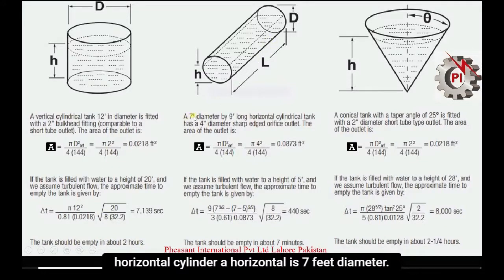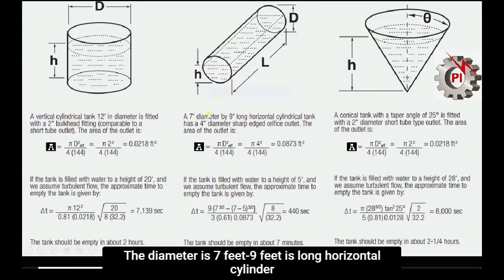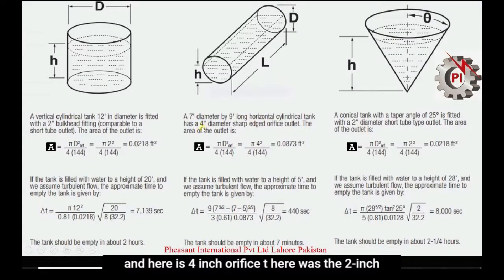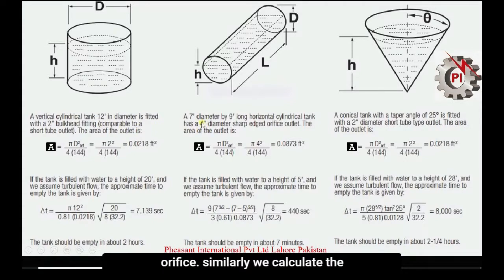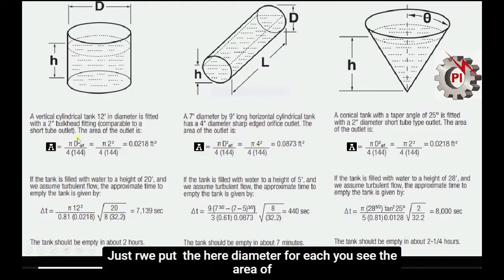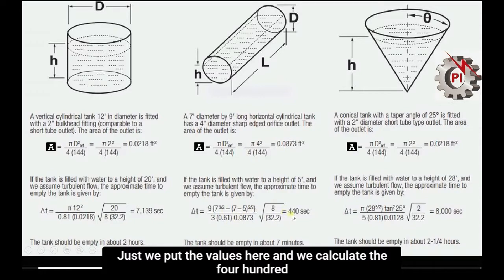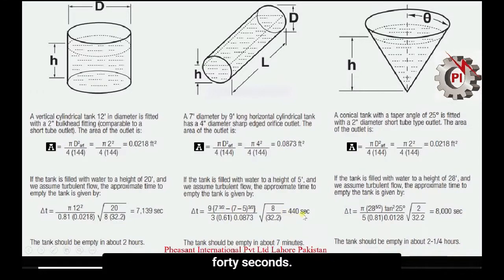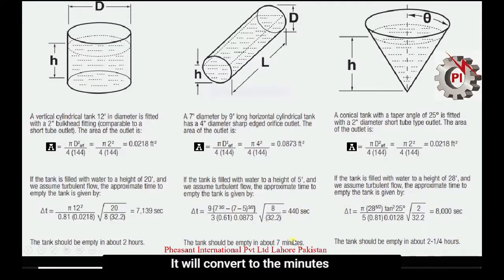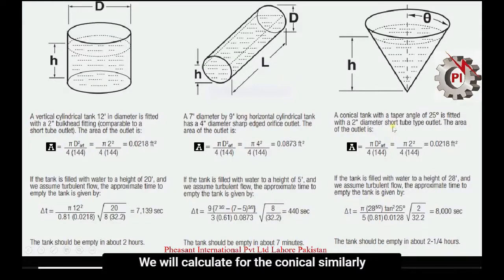After converting from seconds to hours, the tank should be empty in just over two hours. For the horizontal cylinder example, the diameter is 7 feet, the length is 9 feet, and the orifice is 4 inches. We calculate the area of the 4-inch orifice the same way and substitute into the horizontal cylinder formula, obtaining a result of 440 seconds, which we convert to minutes.